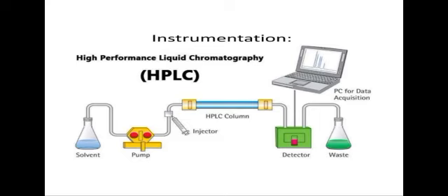Third step, solvent degassing. Several gases are soluble in organic solvents. When solvents are pumped under high pressure, gas bubbles are formed which will interfere with the separation process, steady baseline and shape of peak. Hence, degassing is necessary. The techniques for solvent degassing are vacuum filtration, helium purging, and ultrasonication. These are the techniques we use in solvent degassing.